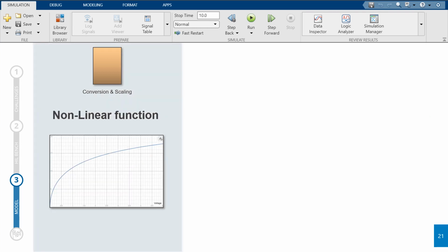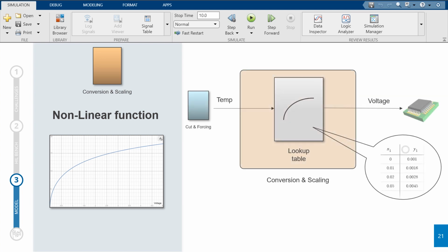In case the conversion function is not linear, we can't use any more the gain and offset to convert engineering values into voltages. In this case, we would rather use the lookup table, which contains discrete values depicting that conversion. The more samples we have in the table, the more accurate the conversion will be.